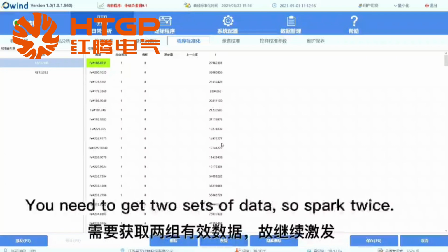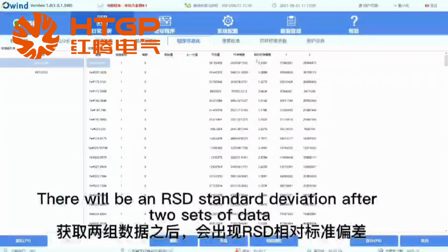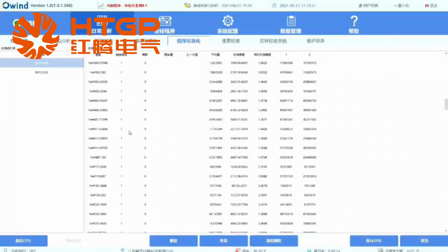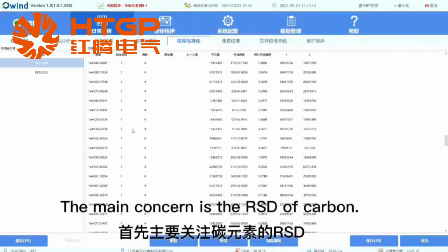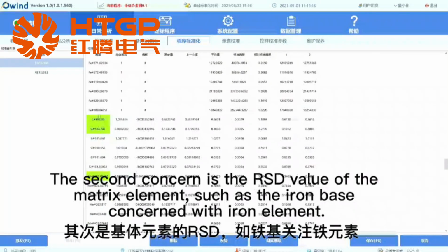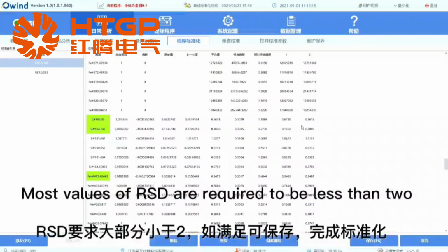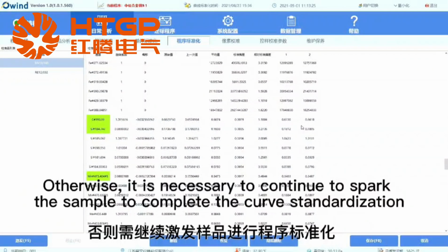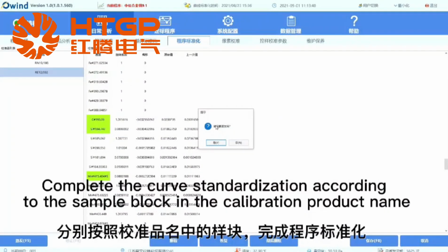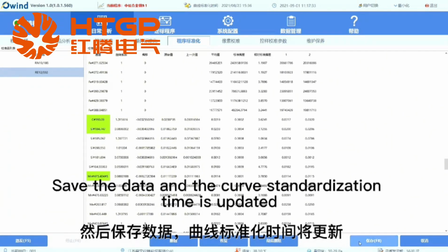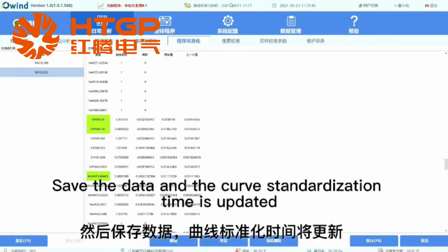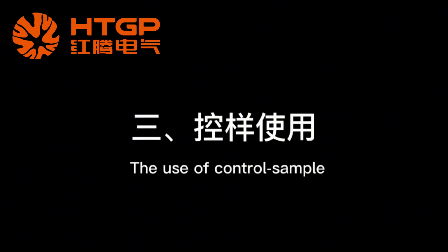You need to get 2 sets of data, so spark twice. There will be an RSD standard deviation after 2 sets of data. The main concern is the RSD of carbon. The second concern is the RSD value of the matrix element, such as the iron base, concerned with iron element. Most values of RSD are required to be less than 2, otherwise, it is necessary to continue to spark the sample to complete the curve standardization. Complete the curve standardization according to the sample block in the calibration product name. Save the data and the curve standardization time is updated.